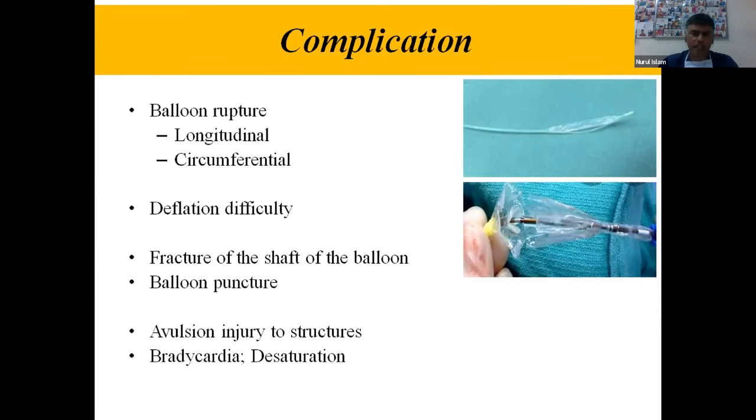During balloon inflation, we should keep in mind some problems can arise, like deflation or inflation difficulties. But the most important is balloon rupture. Once you cross the burst pressure, the balloon can rupture inside, and there will always be a giveaway sensation felt by the operator, and there is a washout of the dye from the balloon area. So the rupture can happen.